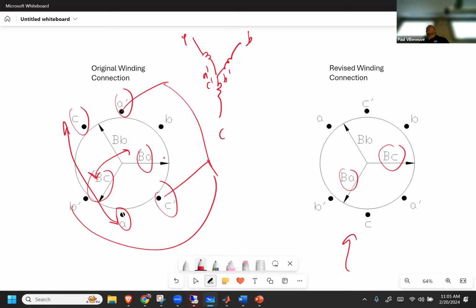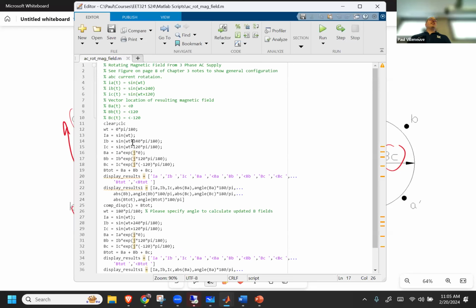What has changed? Does phase A, B, or C current actually change? Not at all. Phase A, B, and C current are all determined by the power supply, so why would those angles change? It's always going to be 0, 120, minus 120, regardless of how it's connected. I don't care what you do with the motor - phase A, B, and C are dictated by the power supply, which dictates all the current going out. So those shouldn't change.